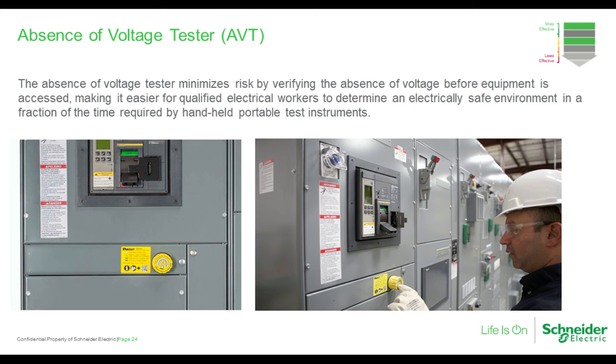And how it works is it takes all of the processes that you would use a traditional meter, a little handheld meter, to test each phase, to test continuity, to test phase to phase, phase to ground, and automates it for you. So it takes a procedure that could usually take around 30 minutes to an hour depending on the application. It requires, again, depending on the application, people to put on extra PPE and be possibly exposed to live parts, and it automates it all and allows you to do it with a push of the button in about 3 seconds. The AVT runs through the test functions in sequence. It tests continuity, voltage, phase to phase on each phase, and phase to ground, and it gives you an indicator telling you that you are working in a safe, de-energized work condition.